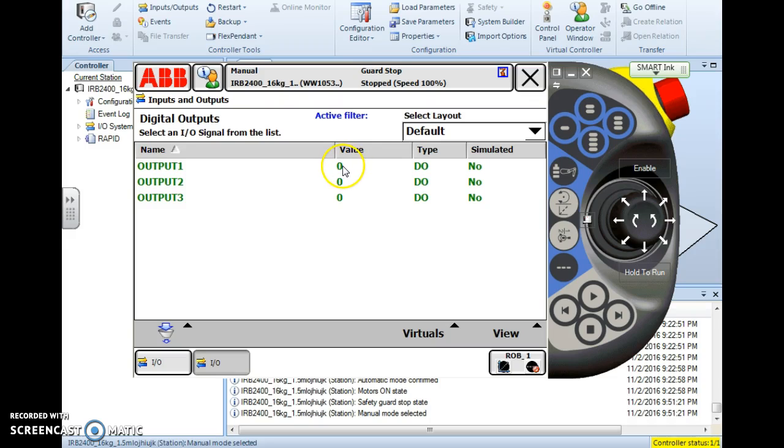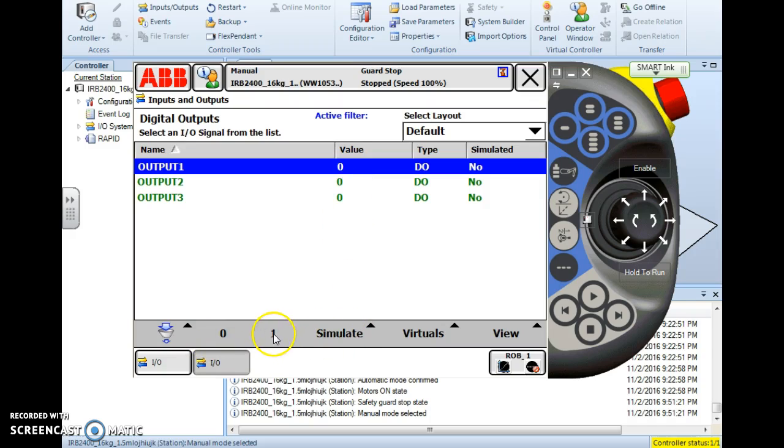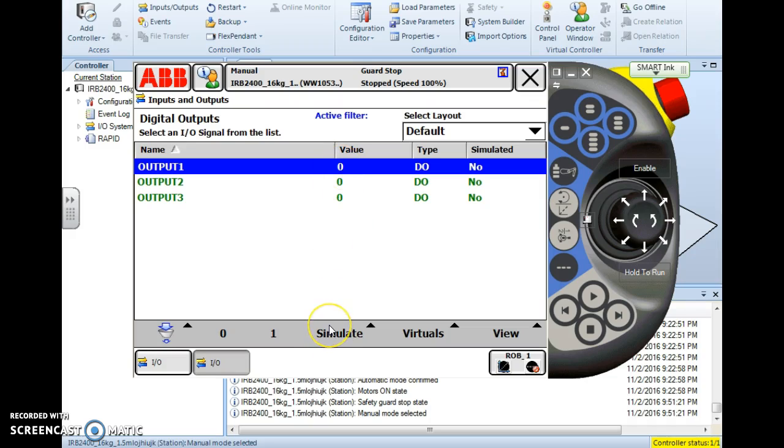Then I simply tap that output and highlight it and I'll notice that I have the option here to simulate it or to physically change the state. If I simulate it then I'm just telling the controller that this is low or high or 1 or 0 and it will not physically change the state.